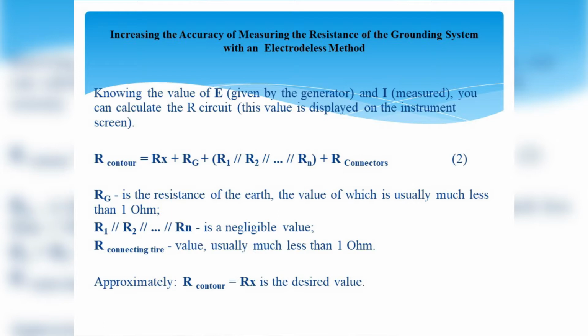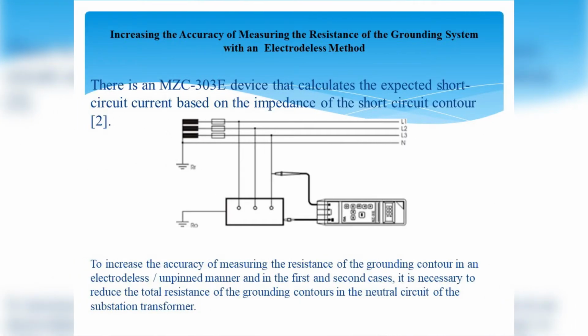This approximation is only permissible when measuring the resistance of the earthing switch above 10 ohm or more. In the figure is shown a device MZC-303E that calculates the expected short circuit current based on the impedance of the short circuit contour. The device is recommended for measurements in electrical installations, networks of buildings, structures and industrial enterprises in which the error caused by neglect of reactive resistance can be of significance.